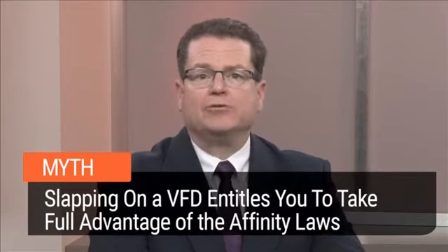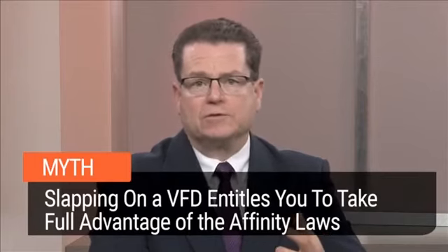Jeanne, I love to study and understand physical principles, and I hate to see them misapplied. In the HVAC industry, the affinity laws are by far the most misapplied of principles. I have to admit that the myth that you slap a VFD onto anything and you get full advantage of the affinity laws is one of my pet peeves.